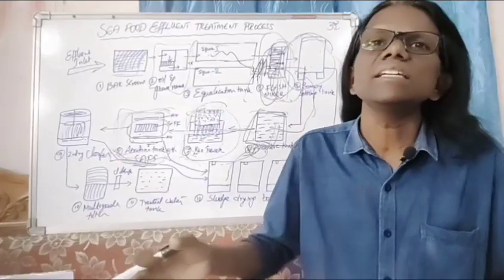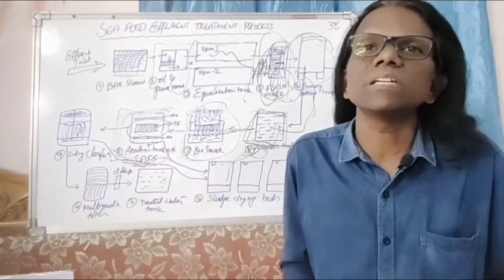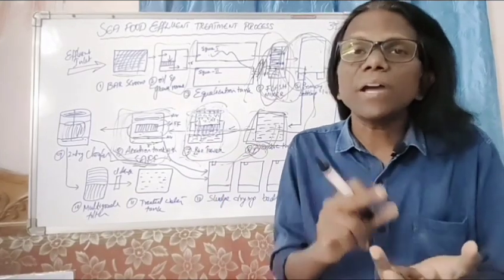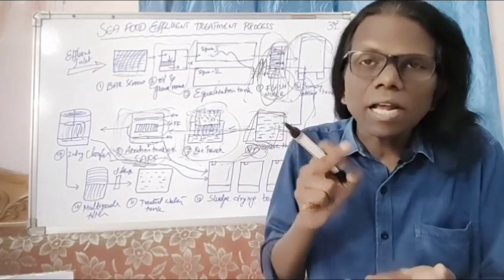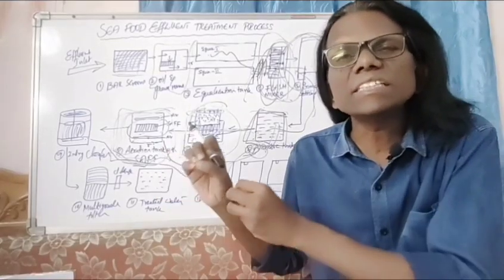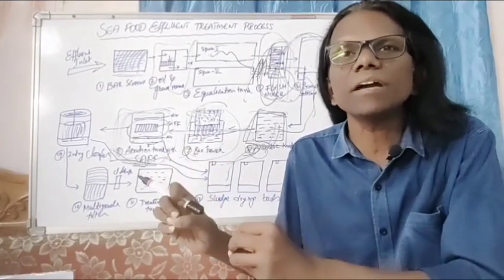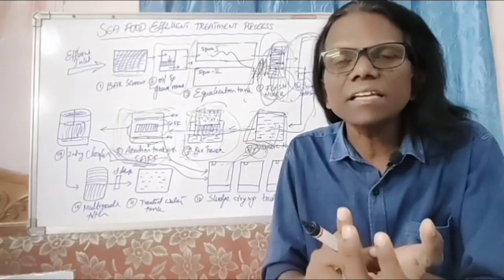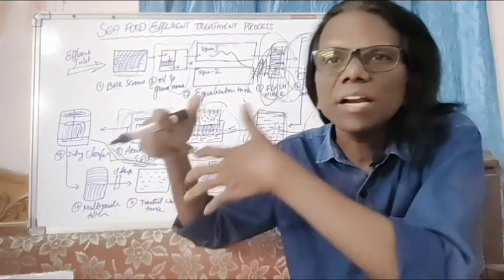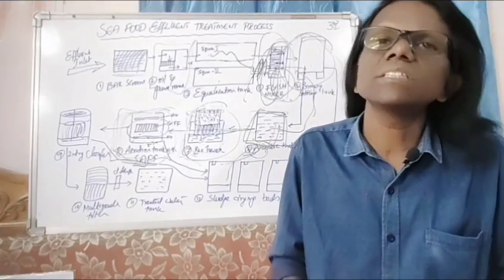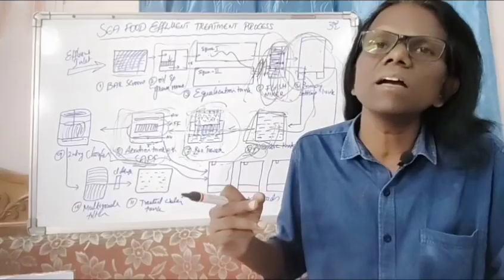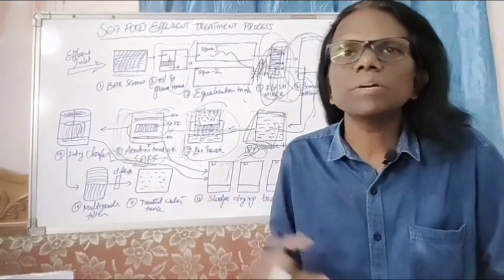Whenever there is a lengthy shutdown period in the processing facility, of more than a few weekdays, make sure you take 5 kg jaggery, mix it with 500 grams of urea and 100 grams of DAP, and add it to the aeration tank regularly. Daily you have to add 5 kg jaggery, 500 grams urea and 100 grams DAP. Dissolve it in water and pour it into the aeration tank, which will generate the feed flow and fulfill the requirements for microbial growth.